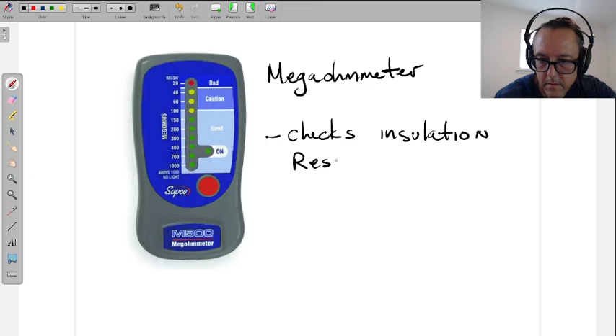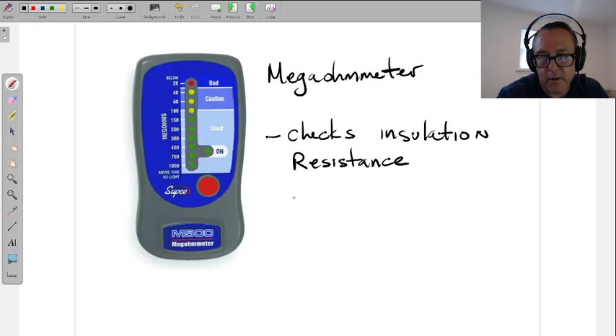This is used for high voltage systems, and also used for motors to check the resistance of the windings, but you guys will learn about that next module. The other two notes I want to write around this one: low resistance output is bad, and high resistance is good.